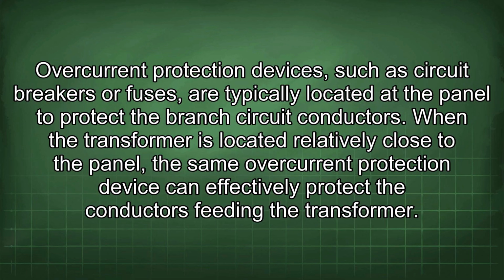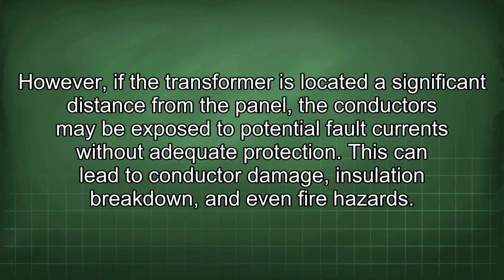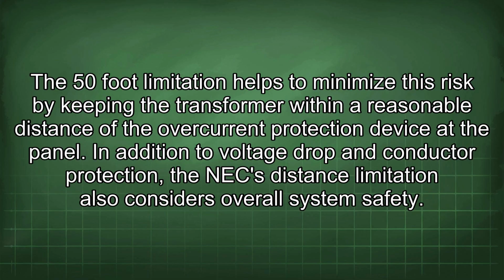conductors feeding the transformer. However, if the transformer is located a significant distance from the panel, the conductors may be exposed to potential fault currents without adequate protection. This can lead to conductor damage, insulation breakdown, and even fire hazards. The 50-foot limitation helps to minimize this risk by keeping the transformer within a reasonable distance of the overcurrent protection device at the panel.